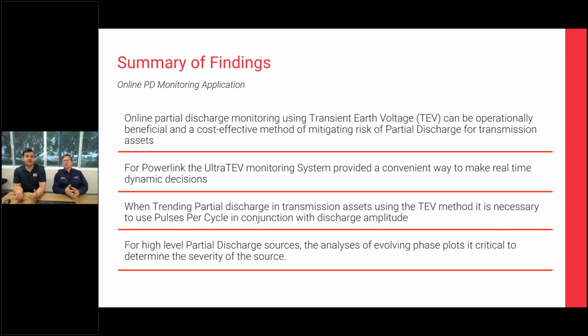From the other side of things, in the transition of permanent monitoring into outdoor yards, we learned a huge amount. One thing we learned and can agree on with Powerlink is that it's a really good method for mitigating the risk of partial discharge in transmission level assets - the risk of failure, the risk of safety to surrounding people. It was a really effective tool that we used with Powerlink to manage this asset. It could have been, and was still quite difficult to manage as a project, but could have been a lot worse.